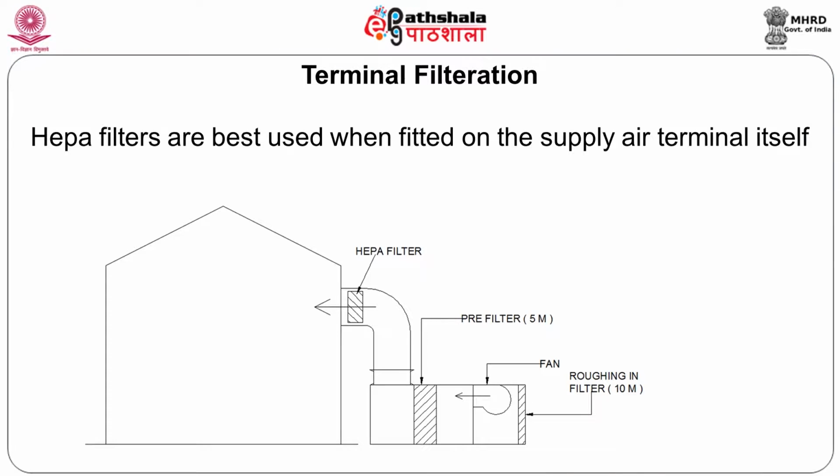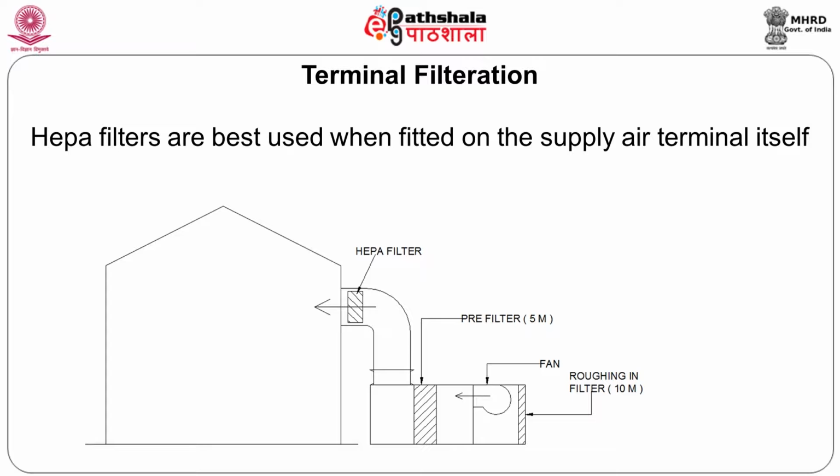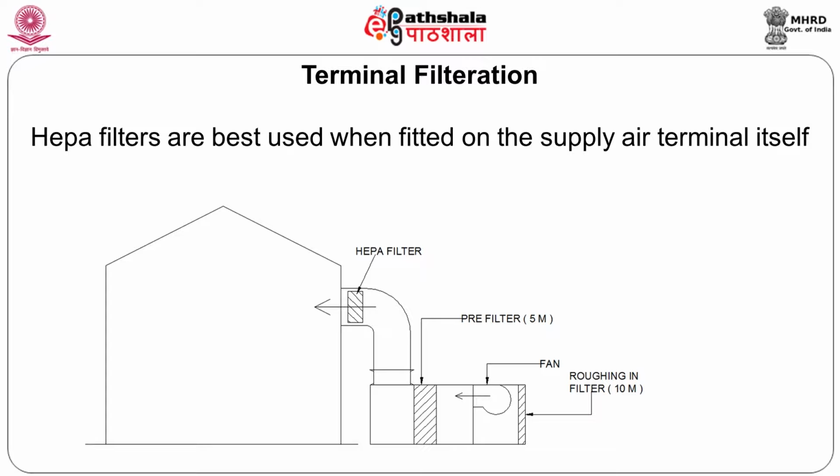So invariably what is done is you look at using a HEPA filter as a terminal filter. Terminal in the sense that, not fatality, terminal in the sense that it is used at the terminal of the air duct. So you would have noticed that in this slide you see the HEPA filter moved right up to the point of entry into the space of interest. So downstream, that means in the machine, you might not have used the machine for a week, some vermin might have bred, it might have left some bacteria, virus, it does not matter because it will get caught on the terminal filter.